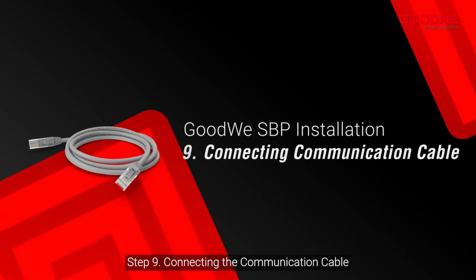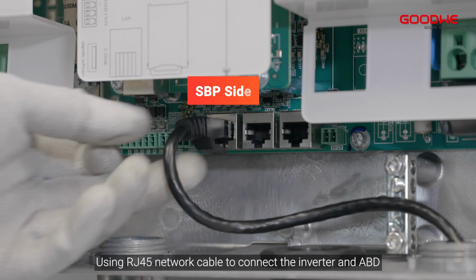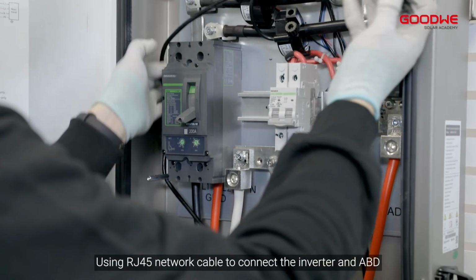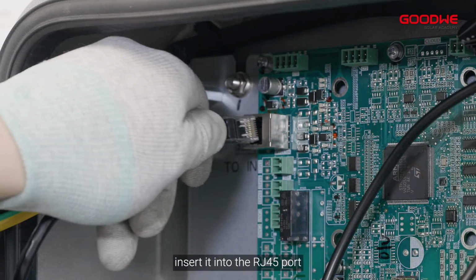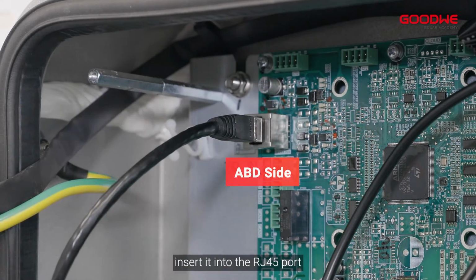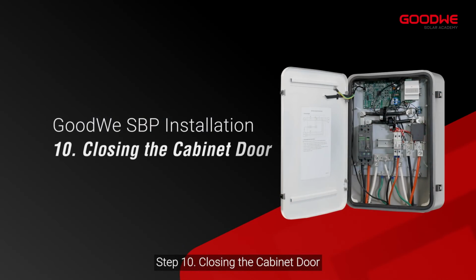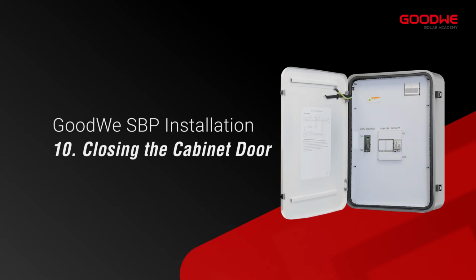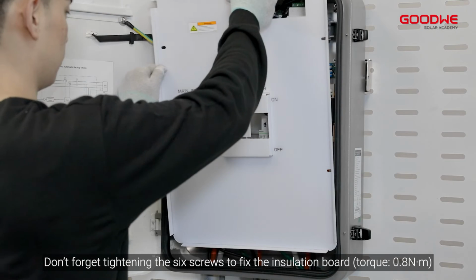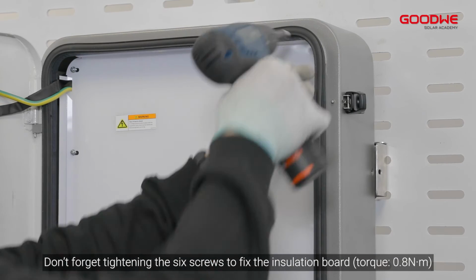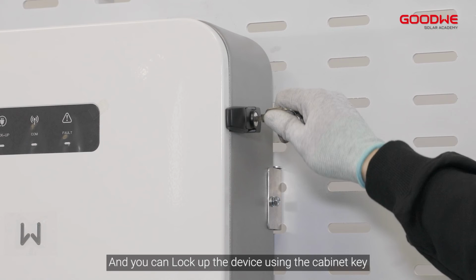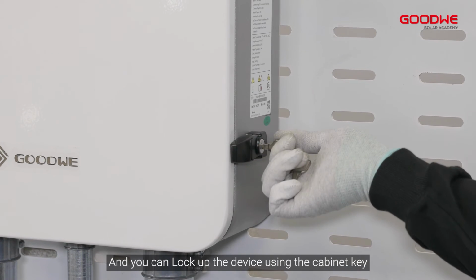Step 9. Connecting the communication cable. Use an RJ45 network cable to connect the inverter and ABD. Insert it into the RJ45 port. Step 10. Closing the cabinet door. After all installation, don't forget to tighten the 6 screws to fix the insulation board. And you can lock up the device using the cabinet key.